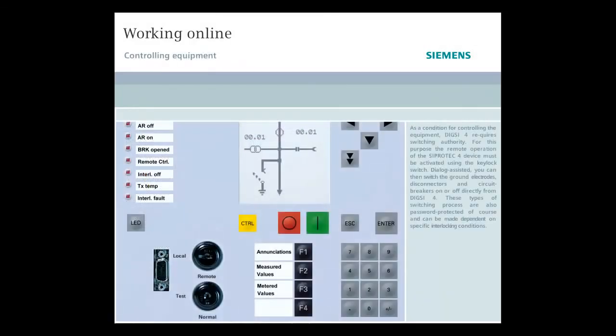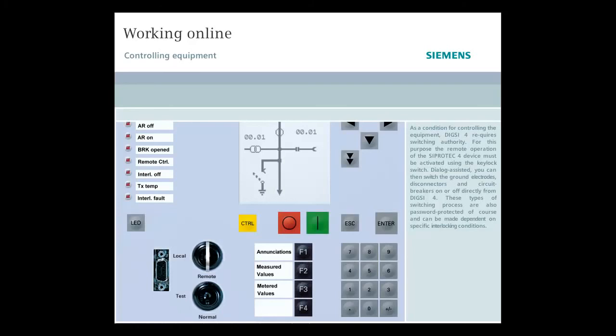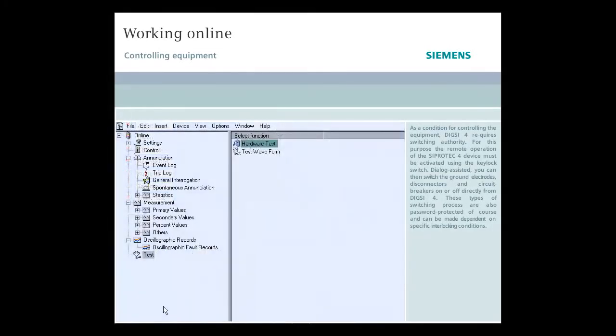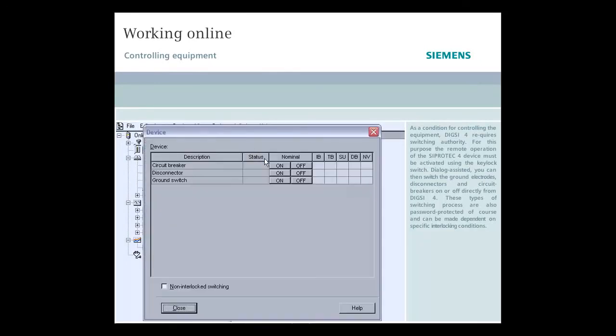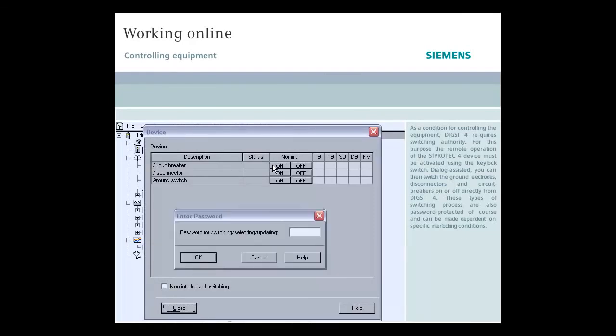As a condition for controlling the equipment, DIGSI 4 requires switching authority. For this purpose, the remote operation of the SIPROTEC 4 device must be activated using the key lock switch. Dialog-assisted, you can then switch the ground electrodes, disconnectors, and circuit breakers on or off directly from DIGSI 4. These types of switching processes are also password protected, of course, and can be made dependent on specific interlocking conditions.